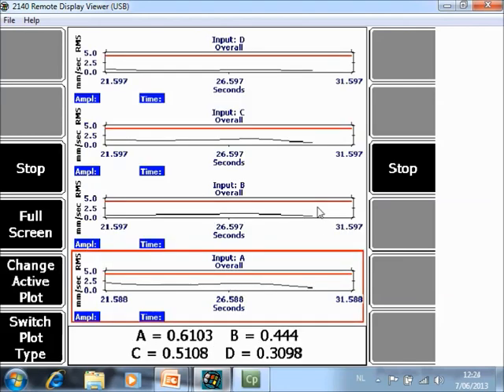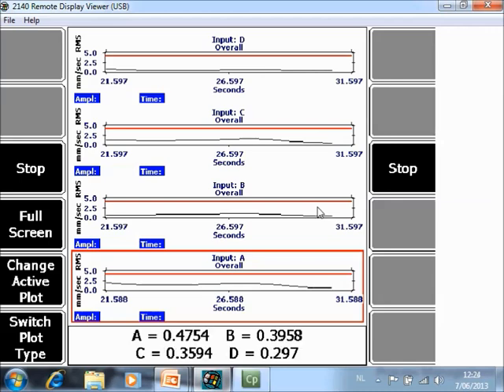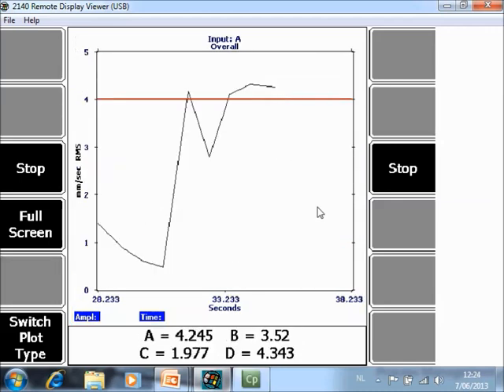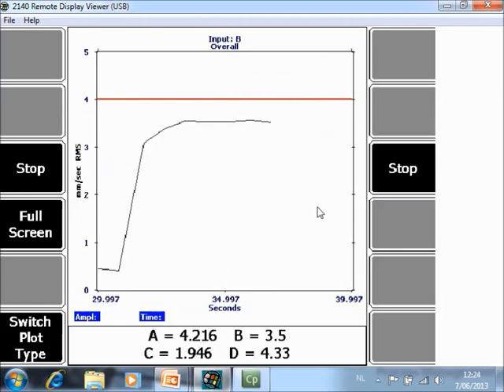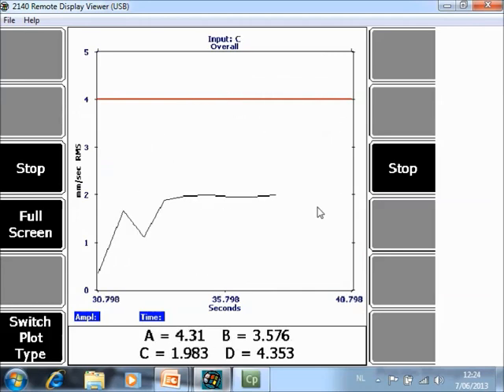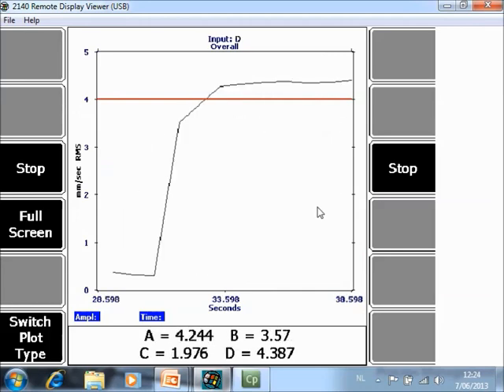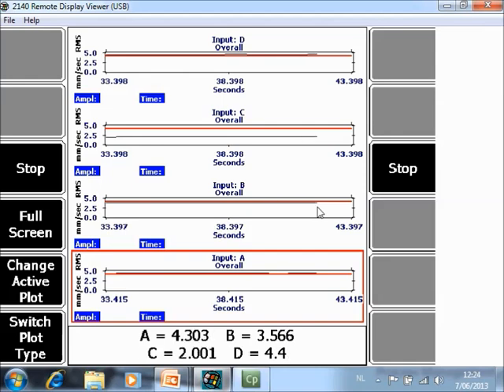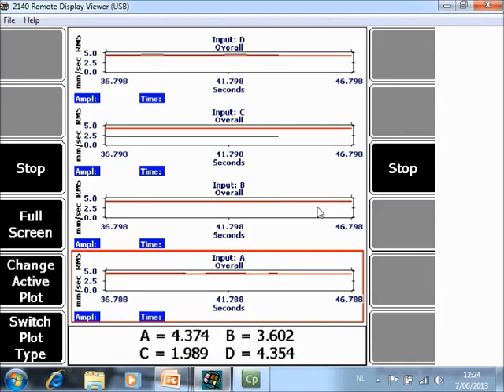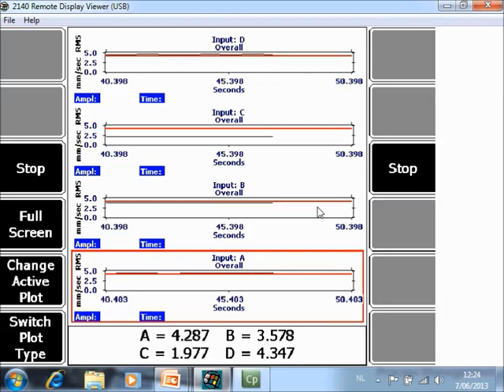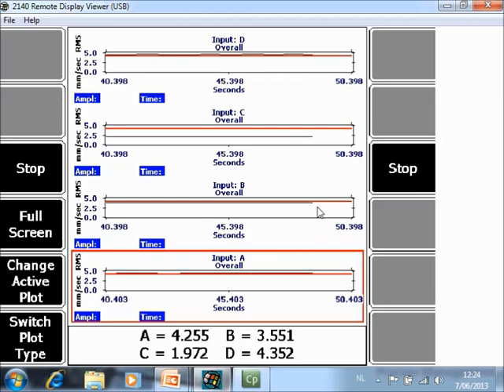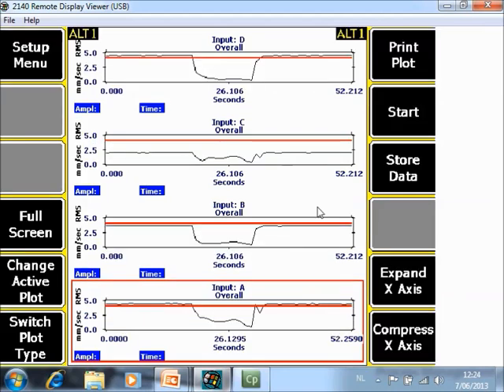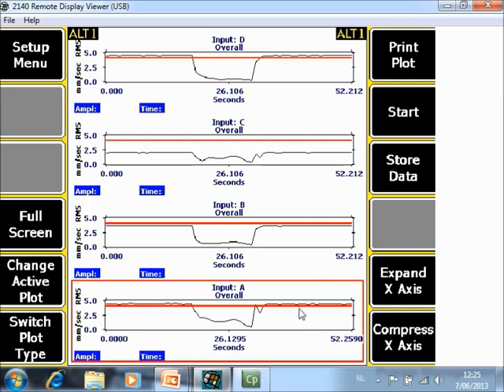Or I start the machine again. And I stop the data collection. And this was the overall value when the machine was running, the shutdown, the start up, and this for your 4 channels. This can be for example on the motor your 2 bearing locations in 2 radial directions.